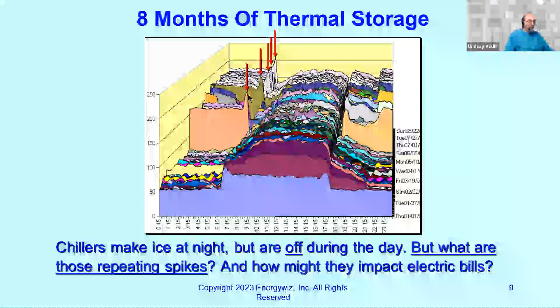Well, what do we do about that? Here's what August looks like after we pruned those spikes. Now, much flatter. All we did was we coordinated the free cooling with the thermal storage so that they turned on their VAV fans, their variable drive fans, opened their outside dampers, but didn't run them at full speed.